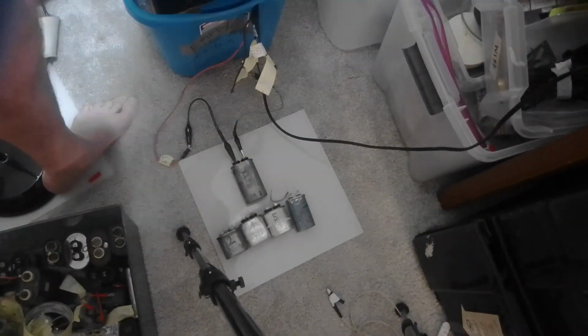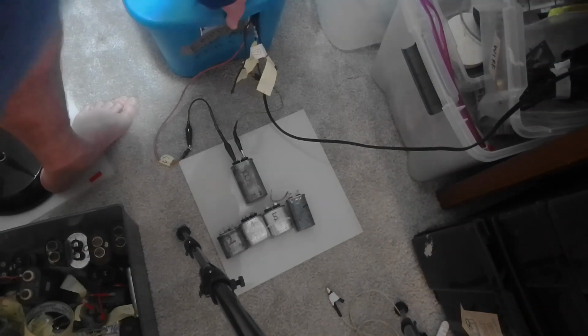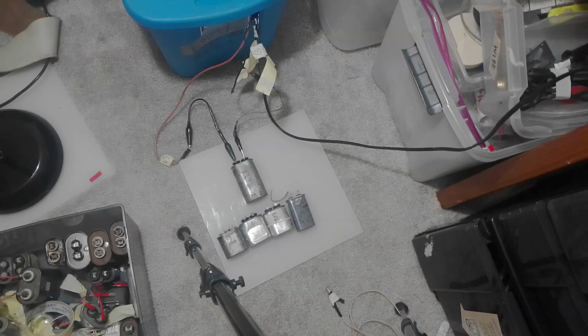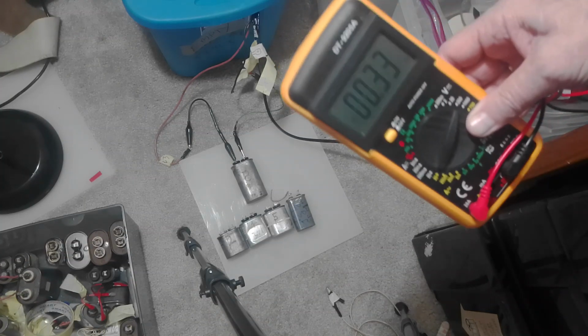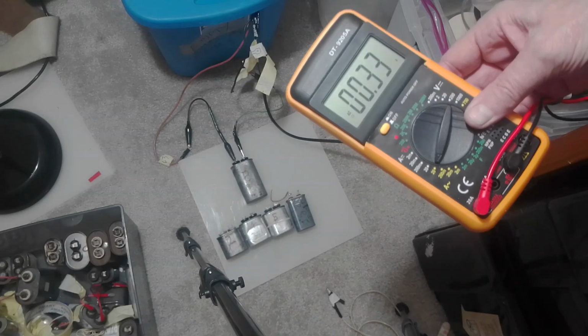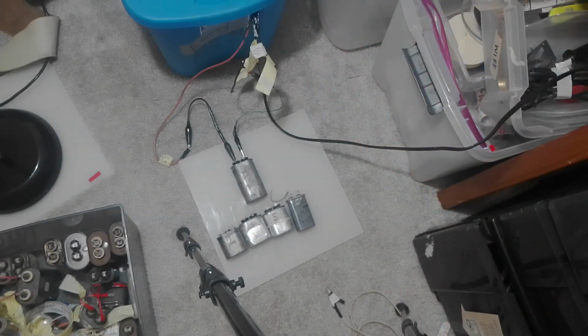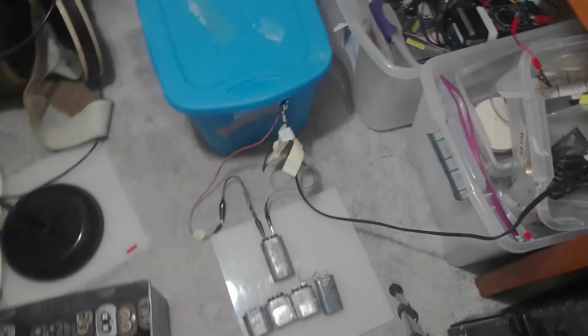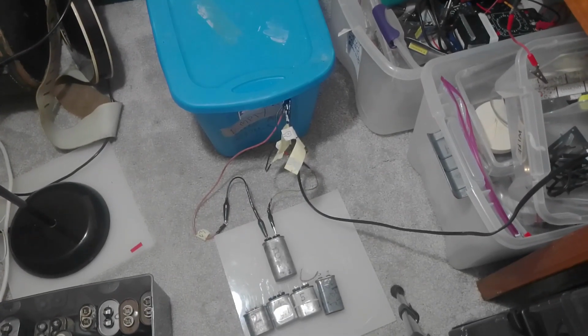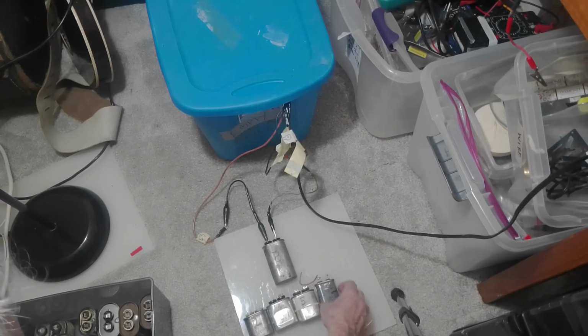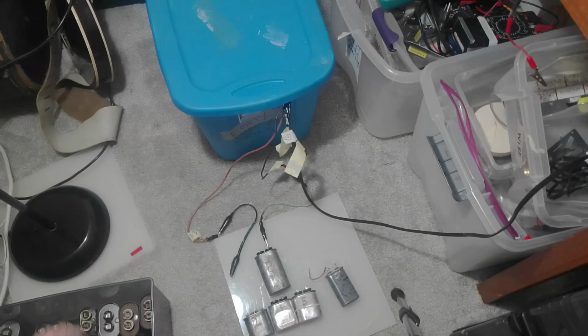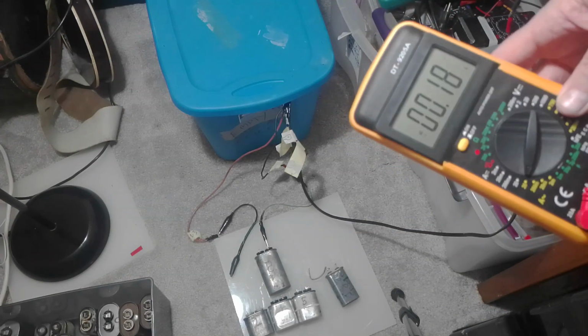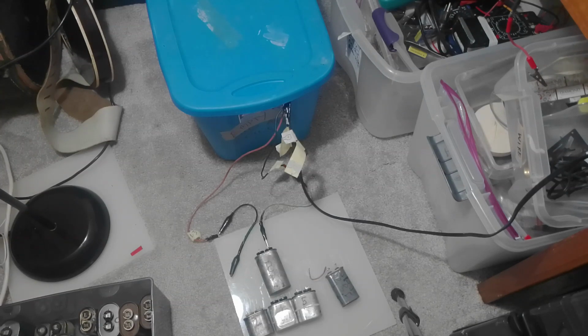Take the lid off. There it is. The amps input is 0.33. It's running on an 8 UF cap. Now I'm going to change the cap value of the run cap to, say, 5. First of all, here it is without any run cap. 0.18. That's no run cap at all.